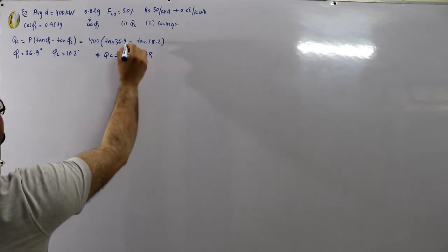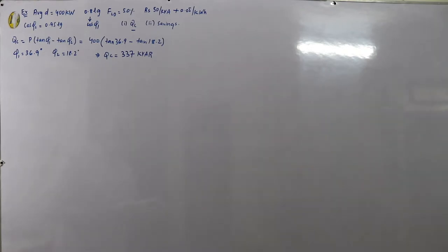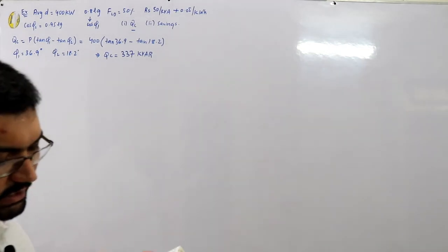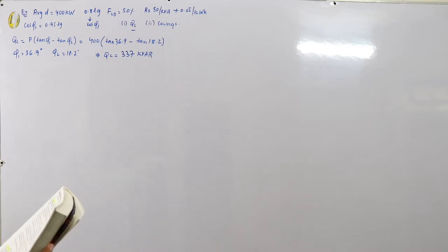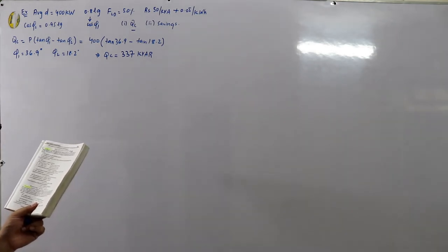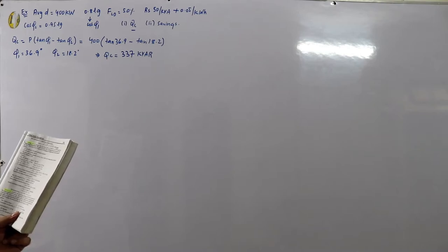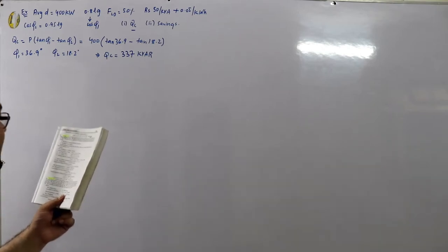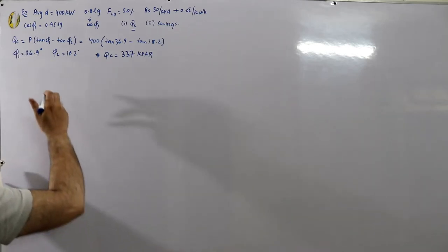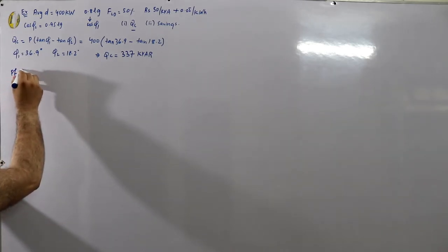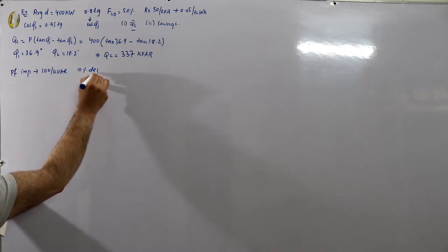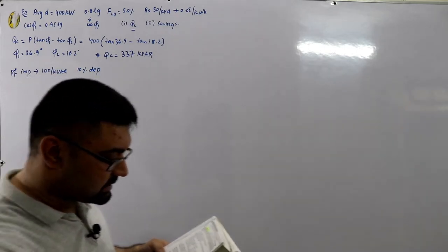Qc = 337 kVArs leading. Now for the savings, we look at before and after power factor correction. The 50 rupees per kVA is the maximum demand charge. The power factor improvement equipment costs rupees 100 per kVAr with 10 percent depreciation annually. We need to calculate the annual savings.